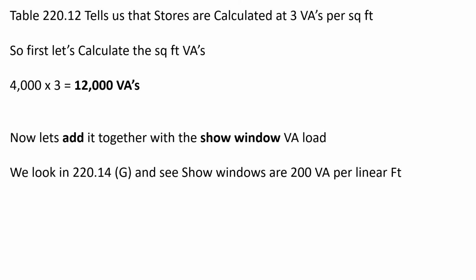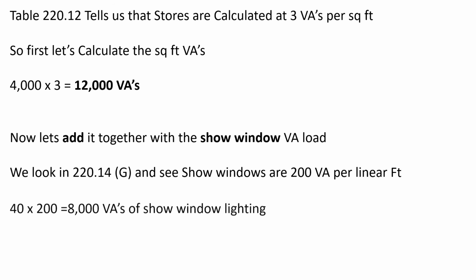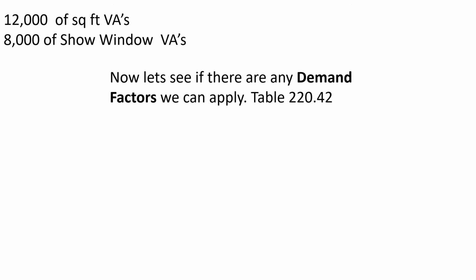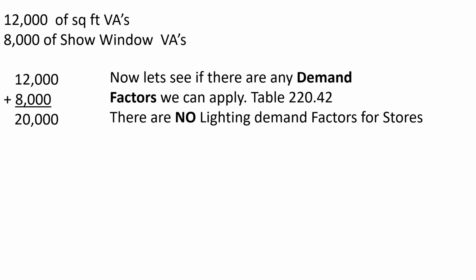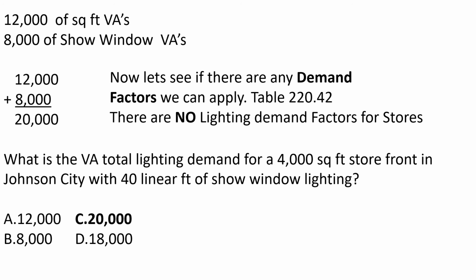We take a look at 220.14(G), and it says that show windows are calculated at 200 VAs per linear foot. So we take 40 multiplied by 200, and that is going to give us 8,000 VAs of show window lighting. Okay, so we have 12,000 square foot VAs and 8,000 of show window lighting VAs. Now let's see if there are any demand factors that we can apply. Let's head to table 220.42. So we look through the types of occupancies. Do you see anything about stores? No. So we just take that total. There are no demand factors for lighting for stores. And we select 20,000 VAs.